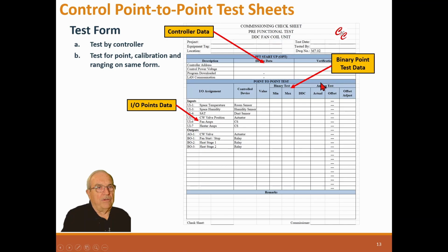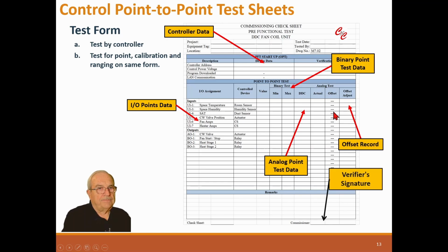This is the binary point test data. It's here, yes, on, open, closed, yes, no. This is the analog point test data. So here's where we test what the system says, what the control graphic says, and what the offset is. And then over here is the verification. We actually put an offset in the machine to do that. And a verifier's signature and notes.